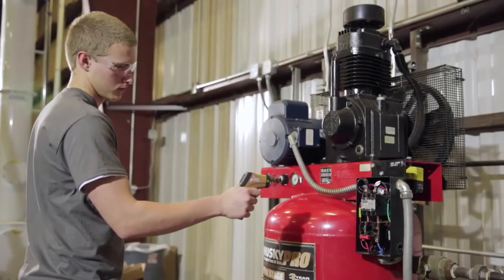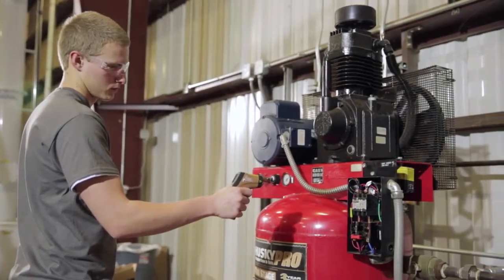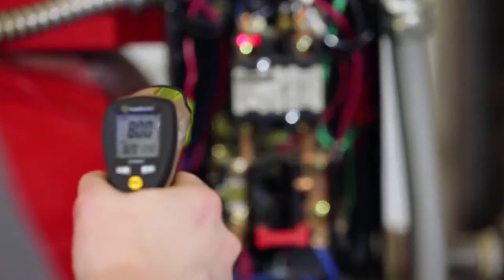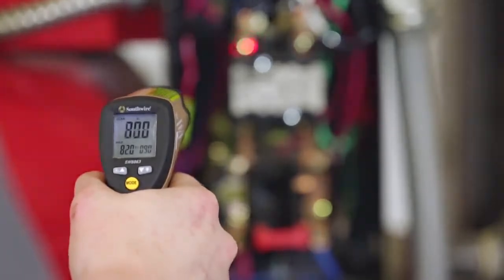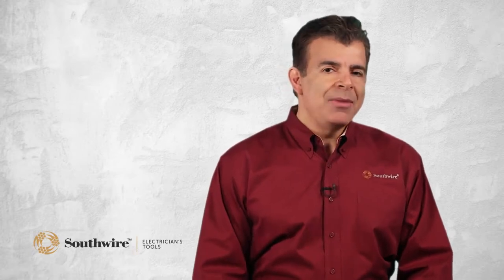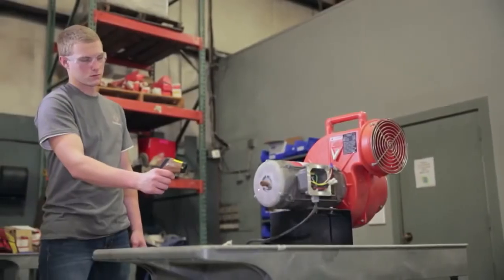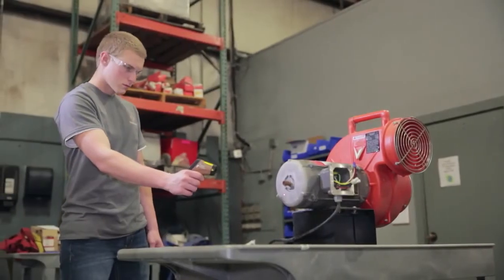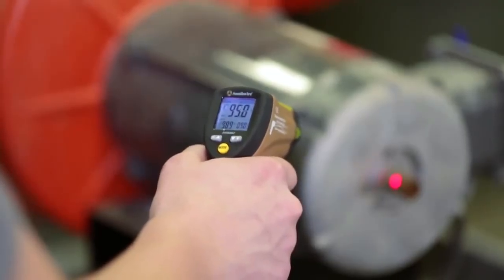Converging laser pointers quickly show the user the optimum measuring distance, allowing accurate spot temperature measurements of an area that is as small as a ½ inch in diameter. This is a very useful feature when trying to locate hotspots on small objects, such as electrical connections, fuses, circuit breakers, motor bearings, and machinery. Another advantage that converging lasers offer is repeatability. By aiming at the same spot from the same distance every time, the user will be able to trend readings over time. For example, if a motor bearing is wearing out, the user will be able to see a temperature rise as the wear increases.